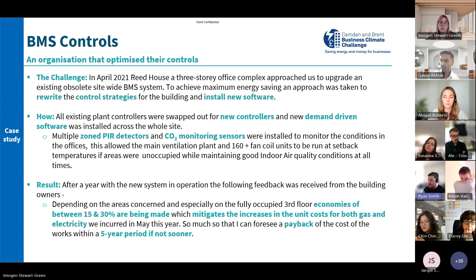So after a year with the new system in operation, the following feedback was received from the building owners. Depending on the areas concerned, and especially on the fully occupied third floor, economies of between 15 and 30% are being made, which mitigates the increase in the unit cost for both gas and electricity they incurred. So much so that they can foresee a payback of the cost of works within a 5-year period, if not sooner. And I'd just like to highlight, this is an example where they've got new controls put in, but a lot of the time your existing controls can just be optimized in terms of schedule or temperatures. So it's a low to no cost measure that can often incur some really good savings as well.